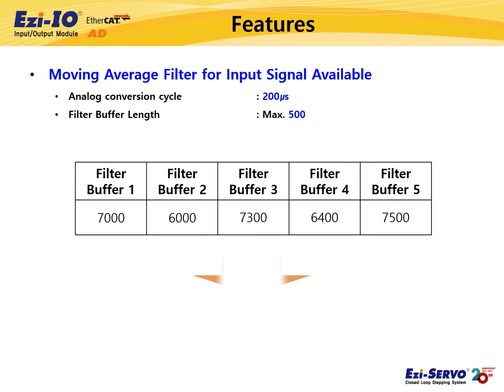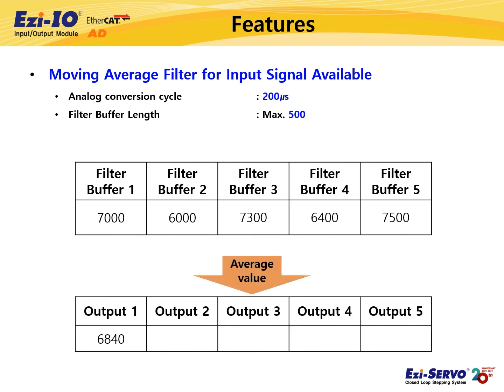I will explain how this moving average filter works using an example of significant analog input data fluctuation due to noise. When the moving average filter function is activated, new analog input data is saved in the filter buffer as a digital value every analog conversion cycle of 200 microseconds. The number of buffers is set with the filter buffer length, and the maximum number of buffers is 500. Here, the filter buffer length is set as 5, so 5 input data values are added and an average value is calculated.